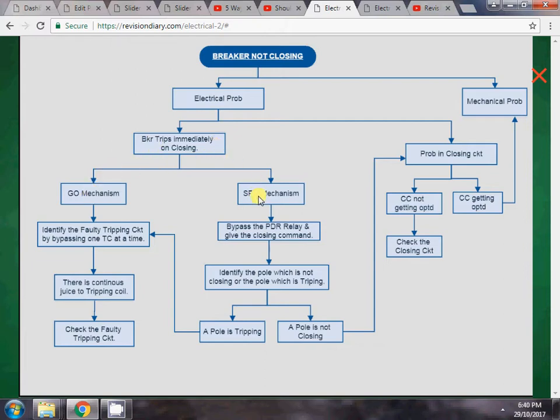For the case where the breaker trips immediately on closing, we consider two types of breaker mechanisms: single pole operated mechanism and gang operated mechanism. In a single pole operated mechanism, each phase has its own operating mechanism, tripping, and closing coil. In a gang operated mechanism, all three phases share a common operating mechanism and a common closing and tripping coil.